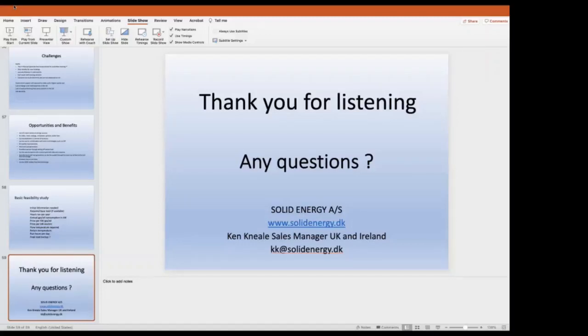A question from Montesino: heat pumps are very good, no doubt, but they are not maintenance free. Could you talk about maintenance, things like cleaning coils and gas charge leaks? Well, you've got me on my strong point. I've spent years servicing and maintaining boilers, CHP, biomass boilers, and although maintenance free is obviously an exaggeration, I was drafting out a maintenance schedule - it's about checking refrigerant levels, checking safety valves, cleaning any leaves away from the evaporators. I jokingly put at the bottom that we'll take some polish and polish the compressor just to show we've been on site, because there's very little to do.